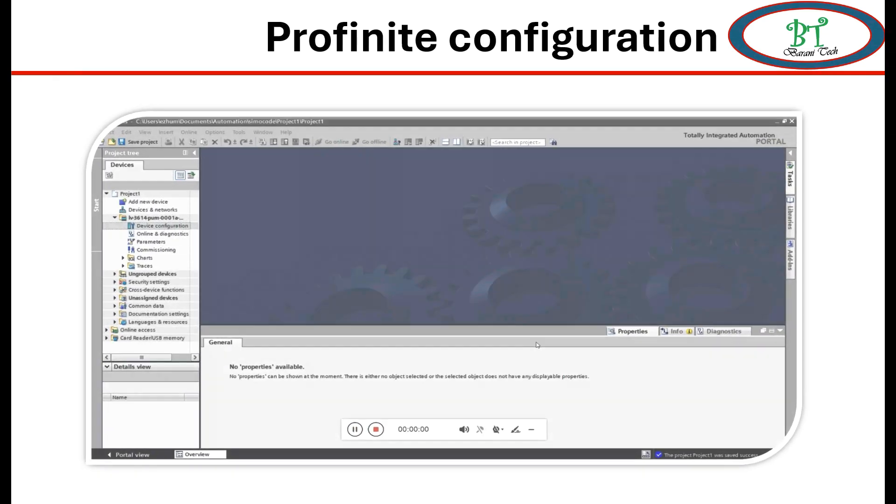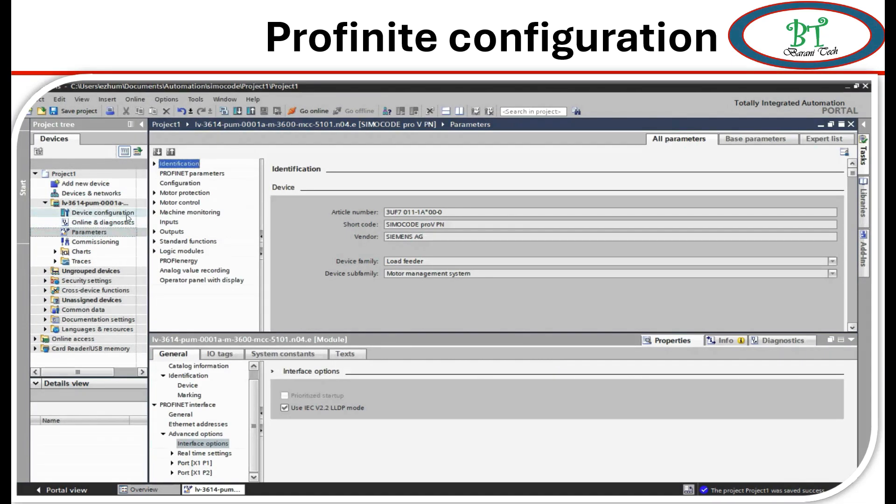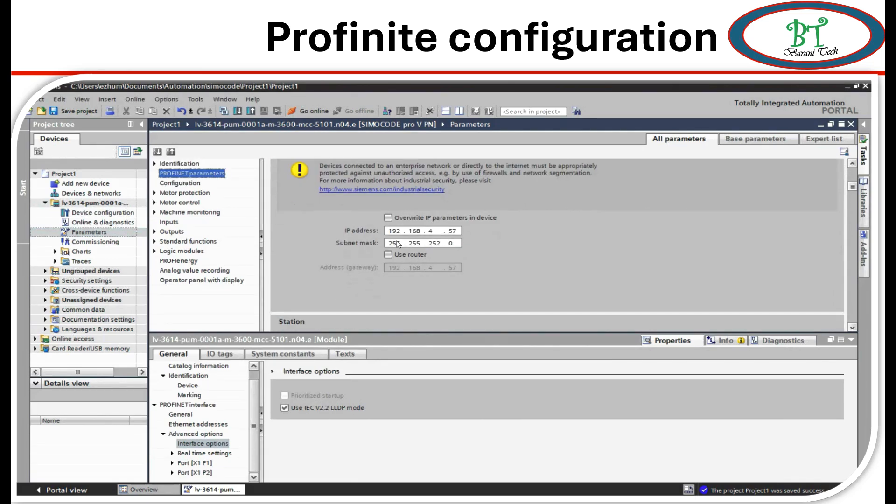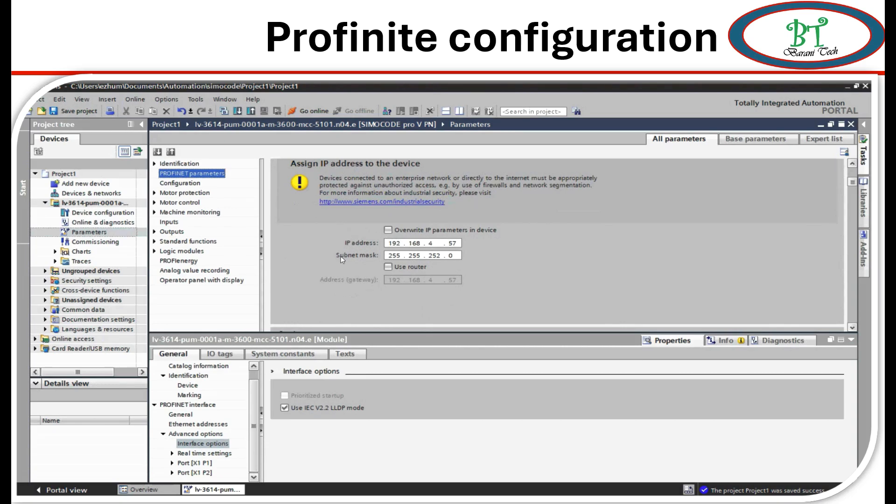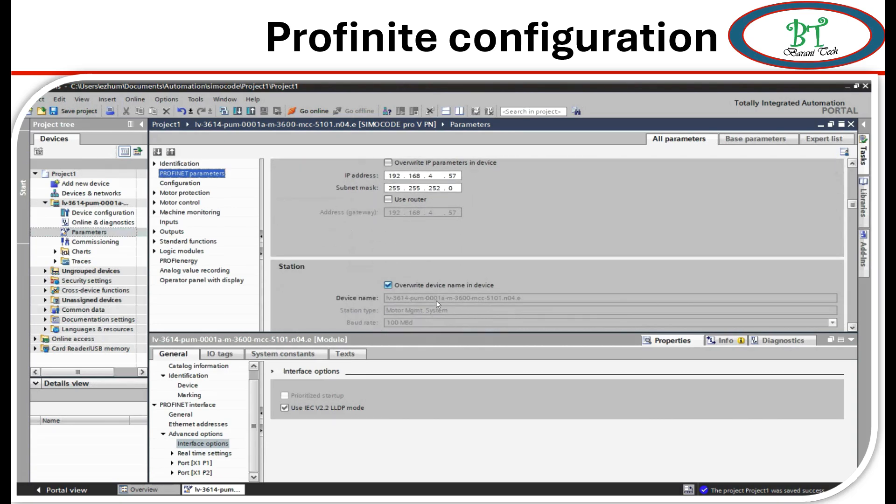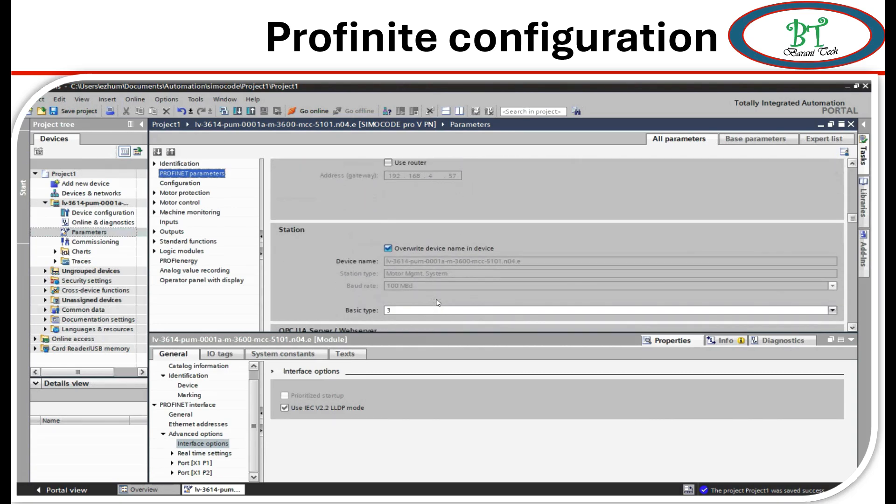Now open the relay software and go to the parameter, then click on PROFINET parameter. Need to check the PROFINET IP address first. Next we go for station device. On station we have to see the device name. This is considered as a PROFINET name and need to ensure this override is enabled.